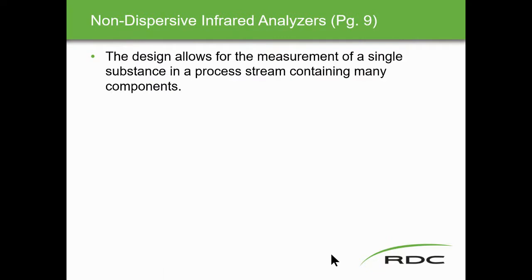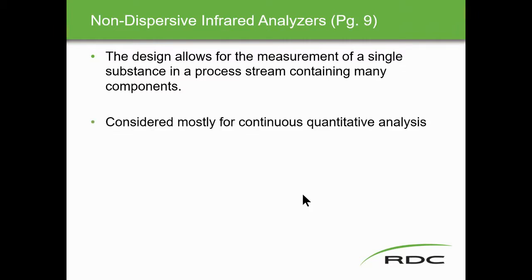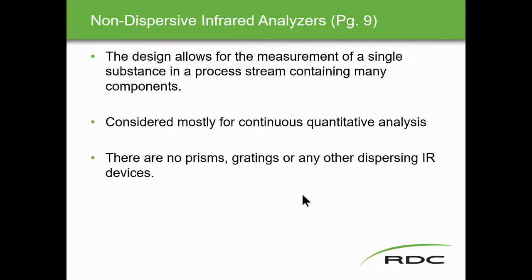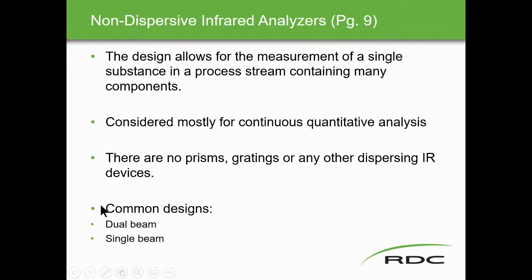Non-dispersive infrared analyzers are designed to allow measurement of a single substance in a process stream containing many components. They are most common for quantitative analysis. There are no prisms, gratings, or other dispersive IR devices on a non-dispersive infrared analyzer. Common designs are dual beam and single beam.